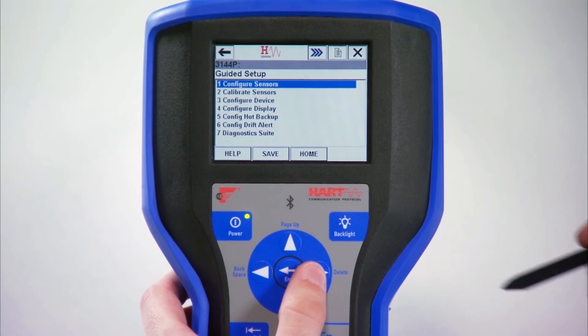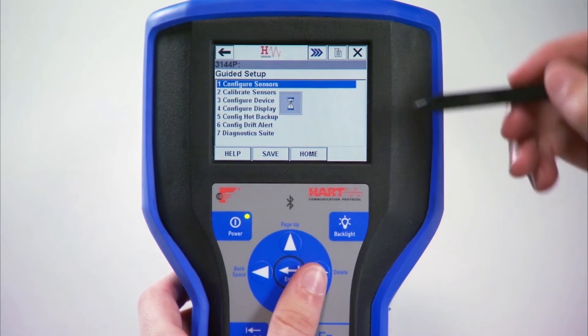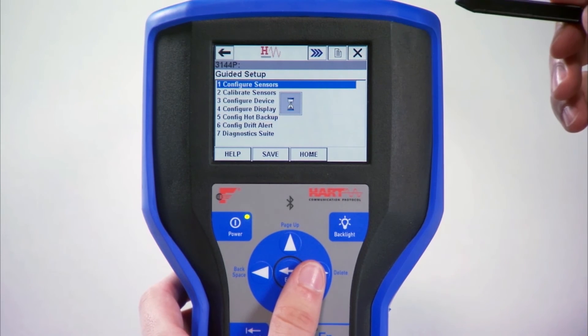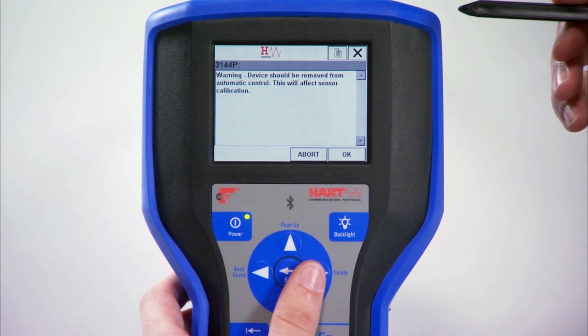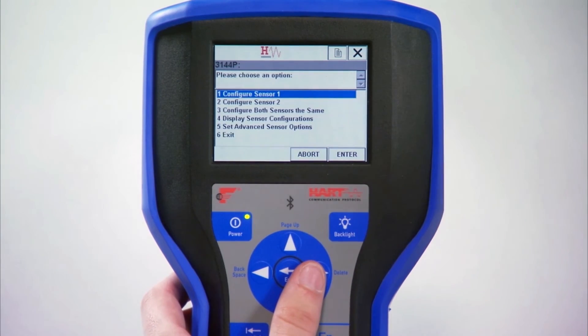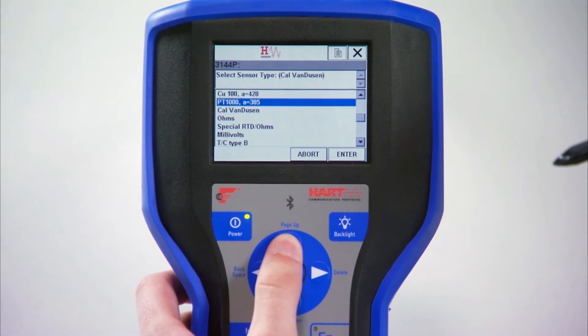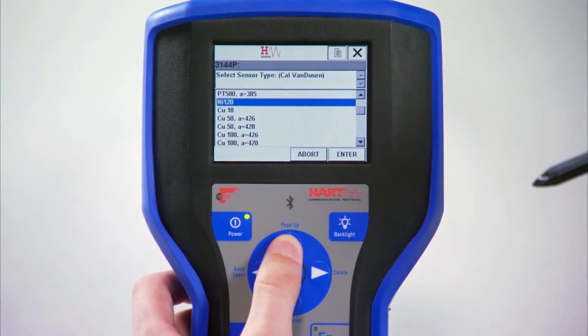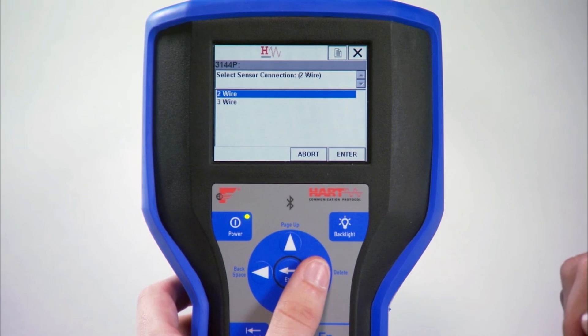A warning screen appears, explaining that the device must be removed from automatic control. Press OK. Then choose Configure Sensor 1 and press Enter. Scroll through the list to find the sensor type of your attached sensor and press Enter. If you selected an RTD, choose the correct number of wires and press Enter.